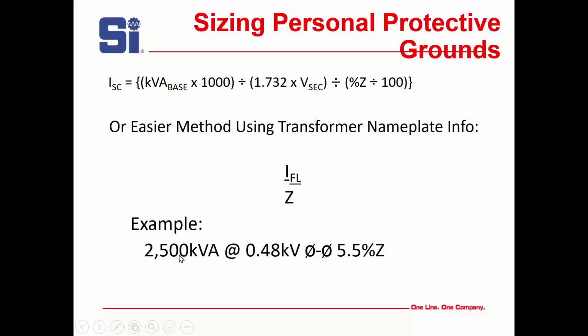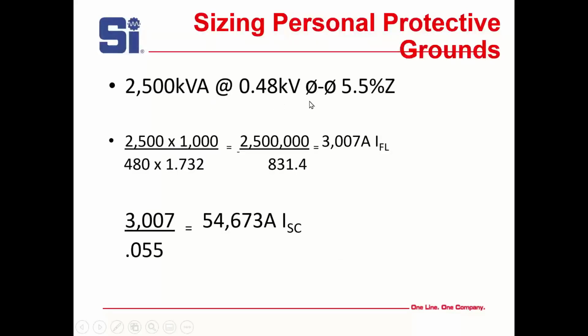So here's an example. I have a 2500 kVA transformer. I got a 480 volt secondary, and my phase-to-phase impedance is 5.5. Pretty regular transformer. Well, you take that information and you put it into your calculation, and you come up with 2,500,000 divided by 831. And I hope you have a calculator. So you come up with 3,007 full load current. Divide that. Now you notice I took that impedance and turned it into a non-percent number, 0.055. And I come up with 54,000. I would round that up to 55,000 myself. That's my short circuit current. And that is what the ground has to carry.